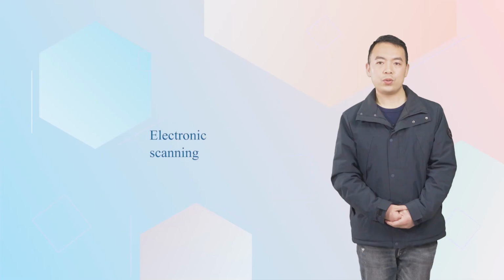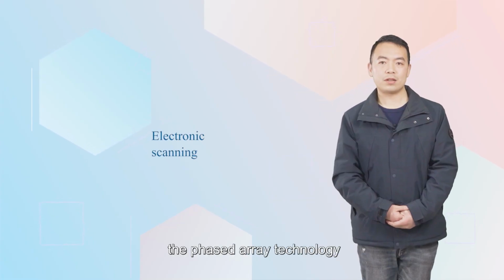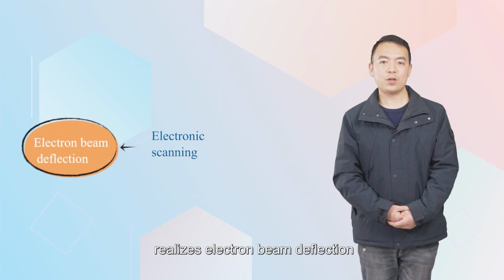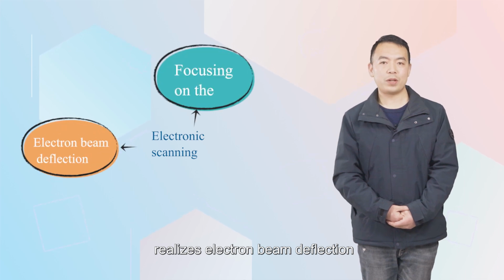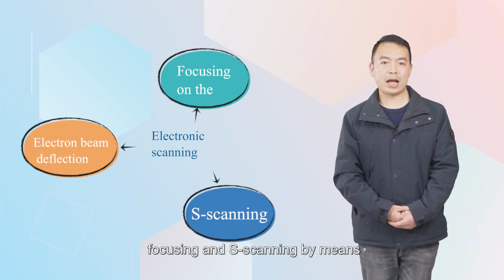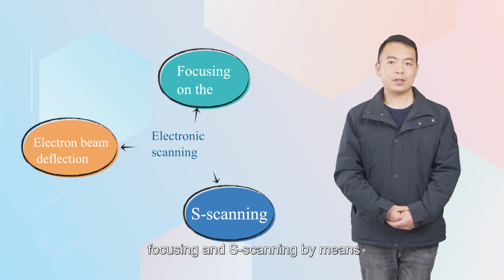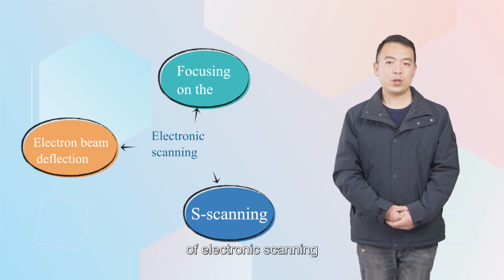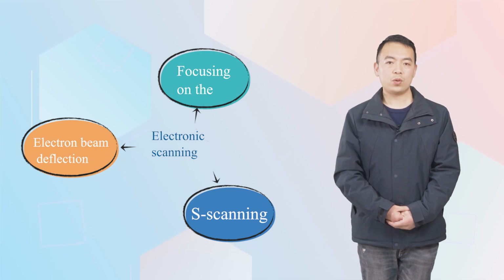To sum up, the phased array technology realizes beam deflection, focusing, and scanning by means of electronic scanning and different focal laws.